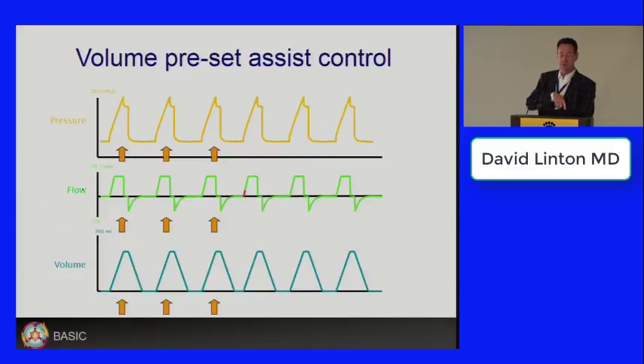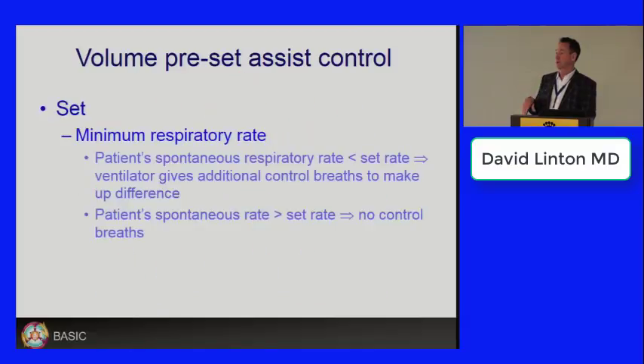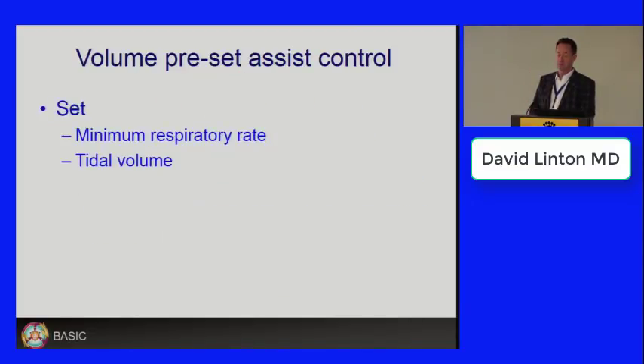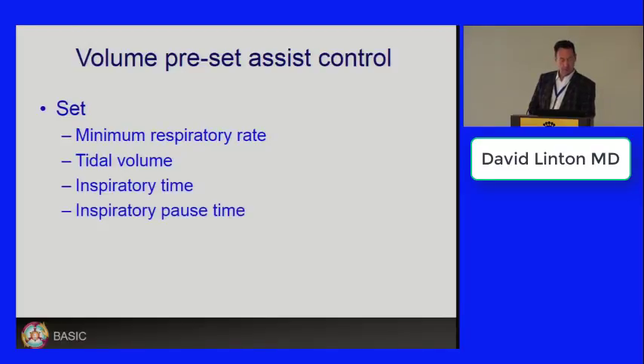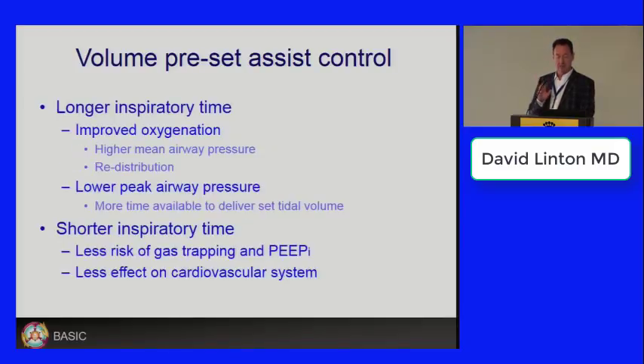So here's a graph of the pressure, flow, and volume showing that it's exactly the same whether the patient is breathing spontaneously or mechanically ventilated. And you set the minimum respiratory rate, okay? Sorry, I keep changing that. Then you set the inspiratory time and the inspiratory pause time, and here comes the problem. Like I said, in my experience, these are the two parameters that are not set properly.